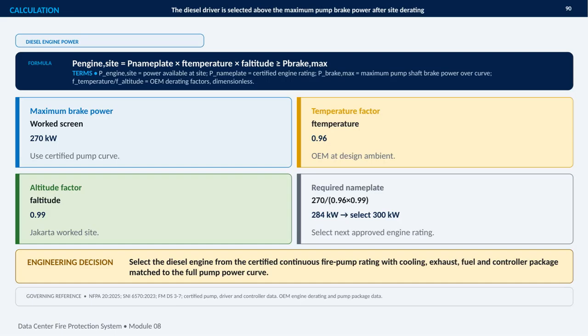This slide shows how we select the diesel engine for the fire pump after accounting for site conditions. The key requirement is that power available at the site, calculated from the certified nameplate rating and the OEM temperature and altitude derating factors, must be at least equal to the pump's maximum brake power. The engine must cover the full certified pump power curve, not just a single operating point.